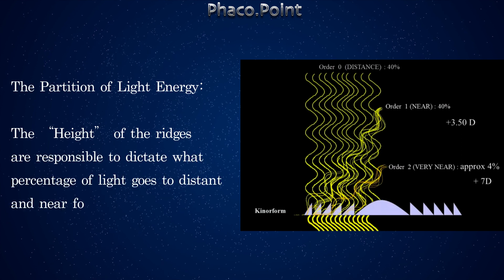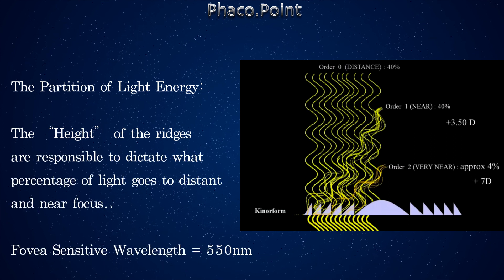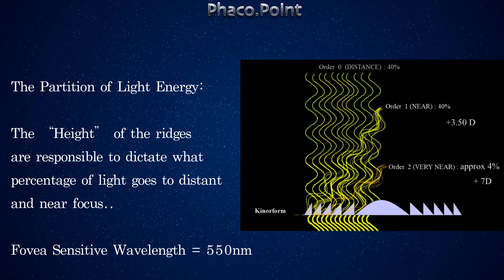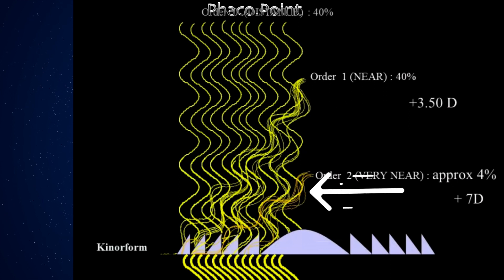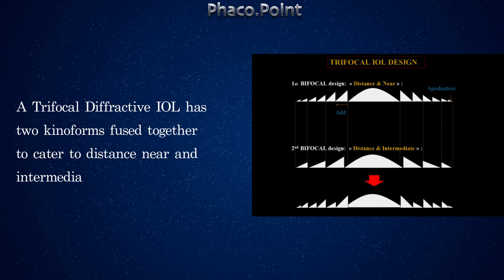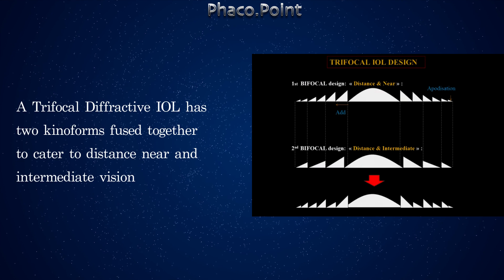The partition of light to go to the distance or near focus depends on the height of the diffractive ridges, governed by the fovea-sensitive wavelength of light, which is about 550 nanometers. If the height of the ridges is set at half the wavelength of light, then the zero order rays — 40% — go undeviated to the distant focus. The first order rays are 40% and go to the near focus, while the second order rays, which are 4%, focus too close to be useful, and the remaining 16% of light energy is simply lost as scatter.